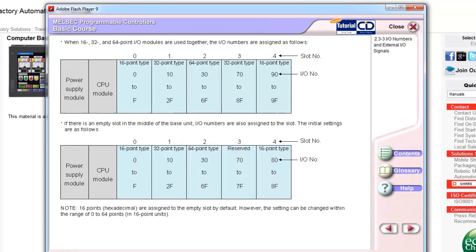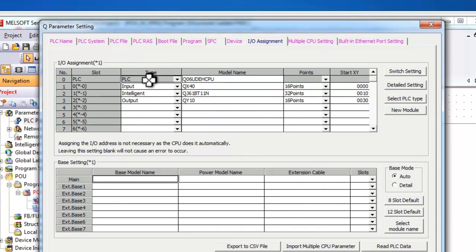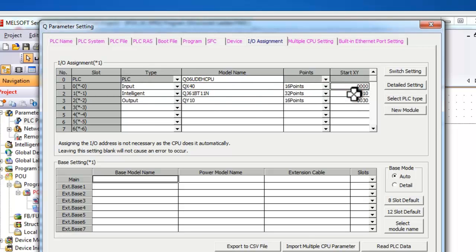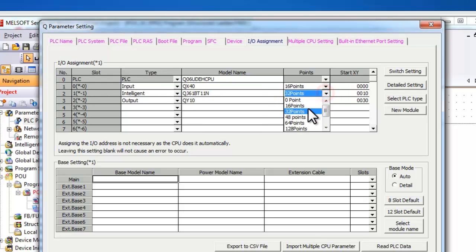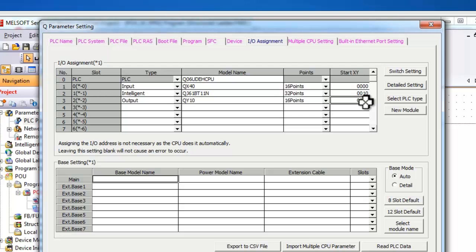An example in the software here is in the IO assignment, in the parameter settings. I have the PLC, and then in slot number 0, I have an input module, a QX40. This occupies 16 points, and I am going to set the start XY to 0. Next, an intelligent module. Intelligent modules occupy 32 points, so you see I have selected 32 points. And my start XY is 10. Now, since this is 32 points, my next start XY address must be 30.